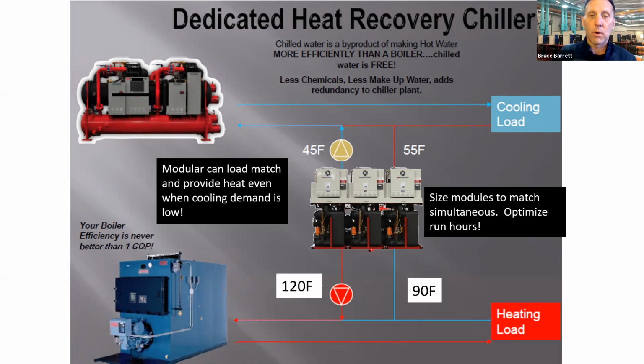We're unloading the boiler, saving a lot of BTUs. Again, COPs of certainly greater than 3, but all the way up to 7. Now I've put 90 and 120 degree hot water. We can do all the way up to 140 degree hot water with a water-to-water heat recovery chiller. So 2 pumps, 4 pipes, very easy installation to do heat recovery and comply with that 90.1 standard on hospitals.